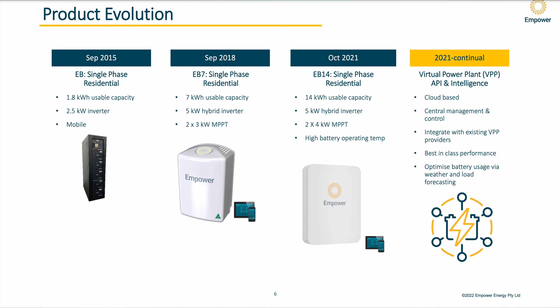So in terms of the ElectroBank 14, we're at sort of 5 kilowatt grid interactive inverter with 2x4 kilowatt MPPT inputs. So 8 kilowatts total. So if your battery's not at 100%, you can charge the battery at 5 kilowatts and still be exporting at 3 kilowatts out of the unit, for example. So the 5 kilowatts is DC input to the battery, and you've also got an inverter function which can be additional PV power to that.